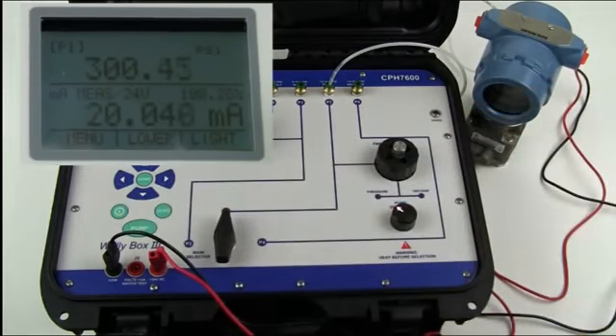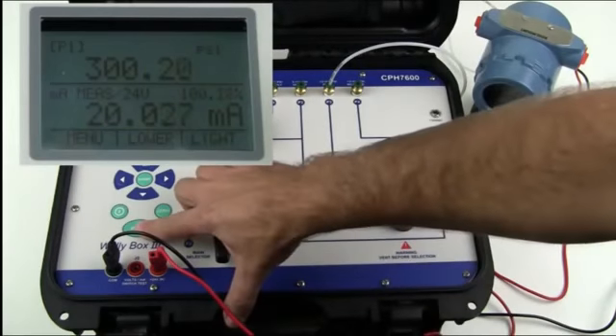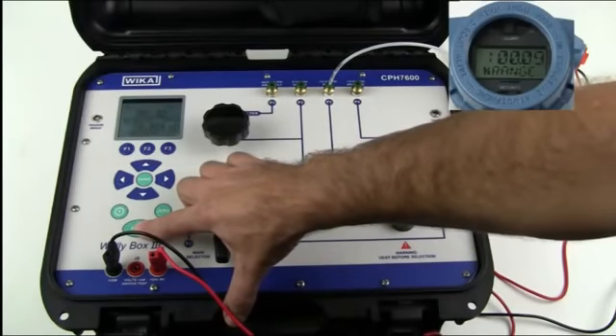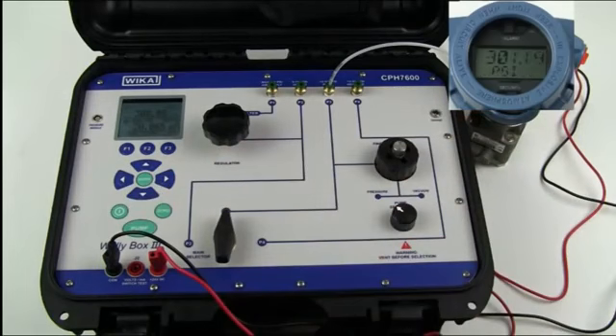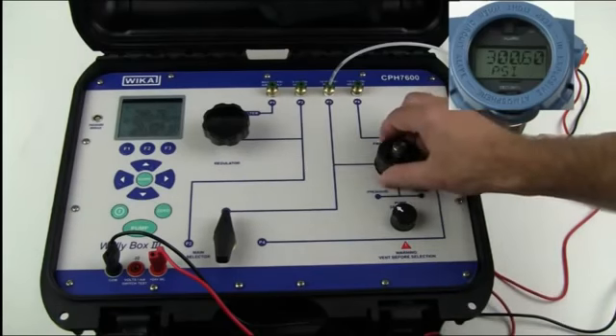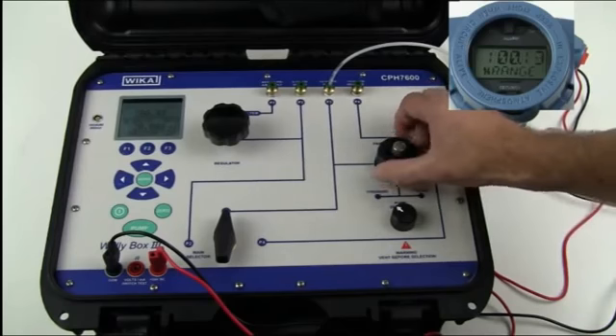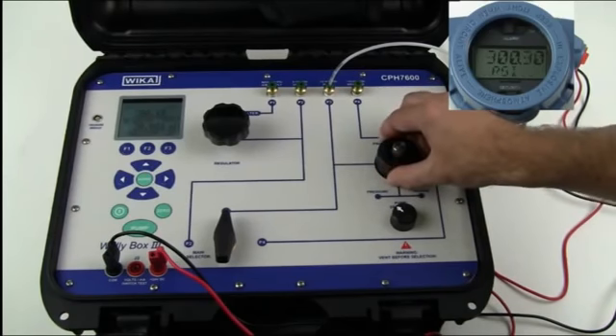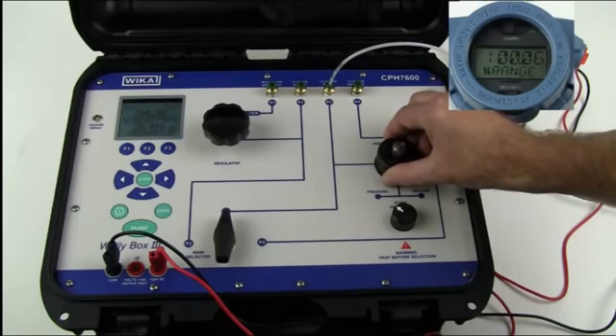You will see the pump did stop automatically and will no longer operate above 300 psi. You will notice the pressure may drop in the beginning due to any cooling of the air in the system. Once it starts to stabilize, you can use the fine adjustment and actually set your transducer to 300 psi. Then you can take the corresponding milliamp measurement.